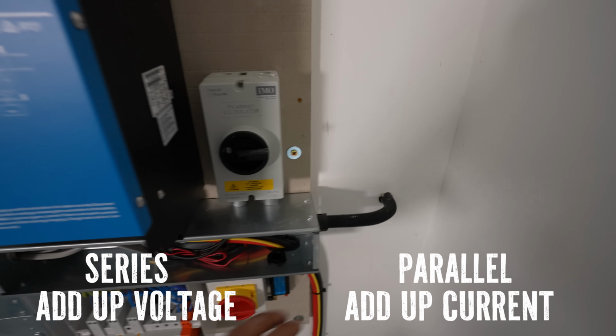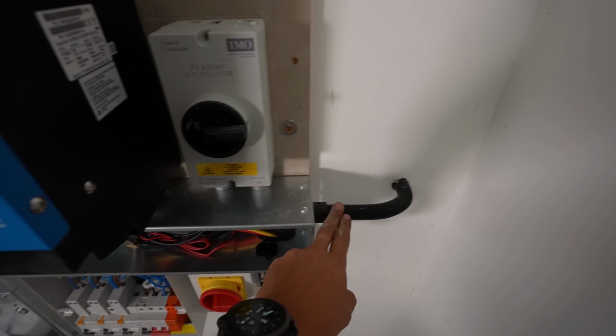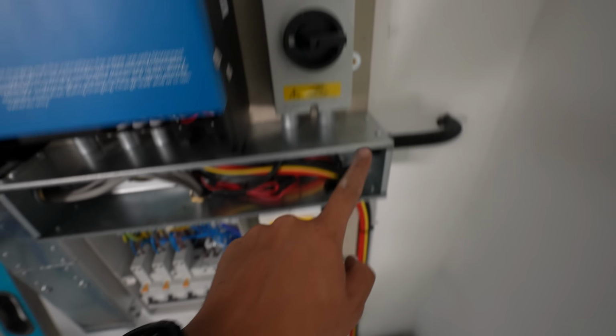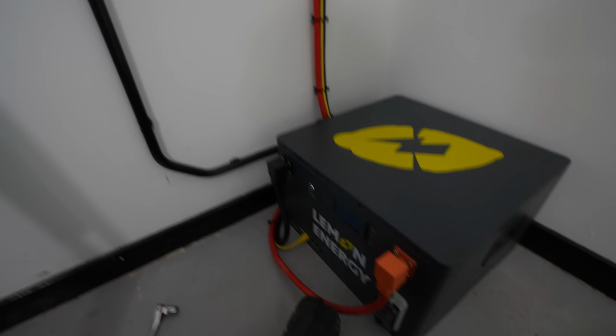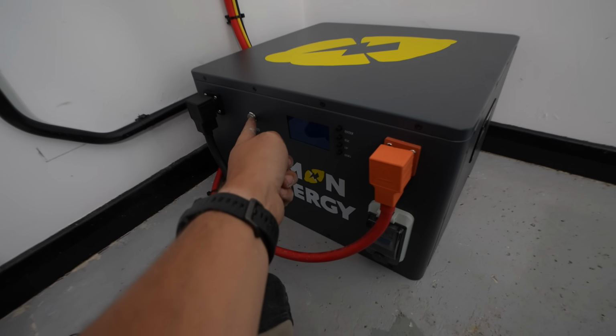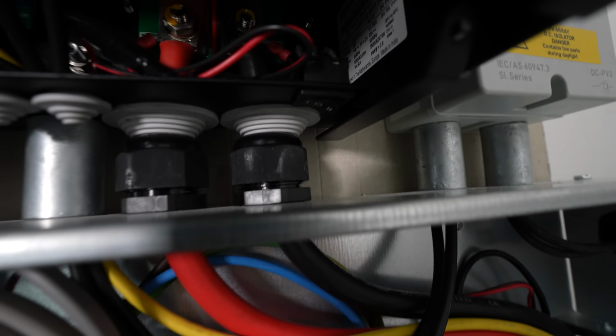So as I mentioned, we've got the cables coming down from the roof inside of a Copex into our DC isolator, but it's connected up via our Easy Solar to the battery. So step 1 when commissioning this system is turning the battery on. We turn that on, turn on our inverter. There's a little hidden dip switch there.